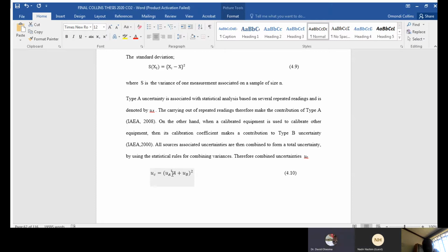Actually, it would be interesting for the Kenya Bureau Secondary Standard Dosimetry Lab, because the systematic uncertainties arise from the uncertainties associated with the nature of the measurement apparatus, assumptions made by the experimenter, or the model used to make inferences based on the observed data. So there are those three issues: the nature of the measurement apparatus, let's say the chamber you use, and the assumptions made by the experimenter. The way you measure is not the way I will measure, is not the way Daktari will measure.